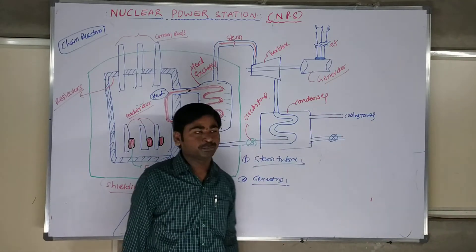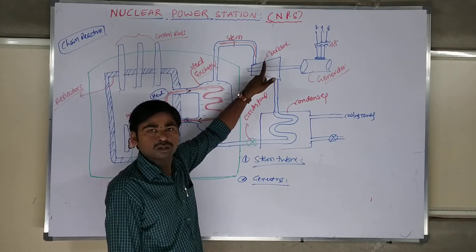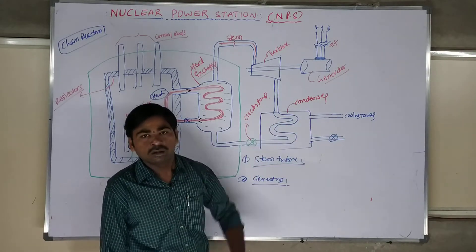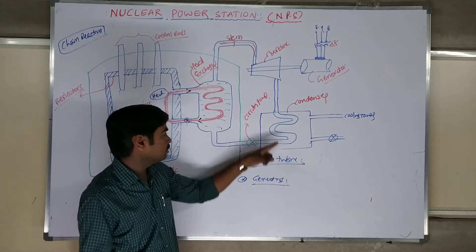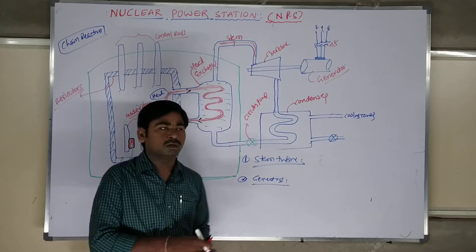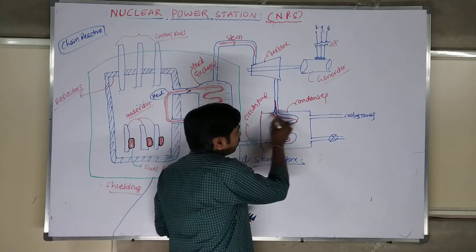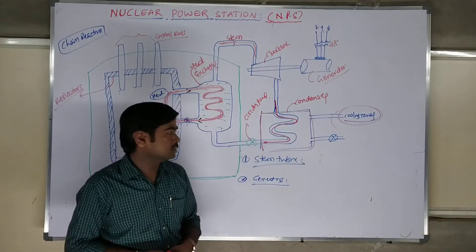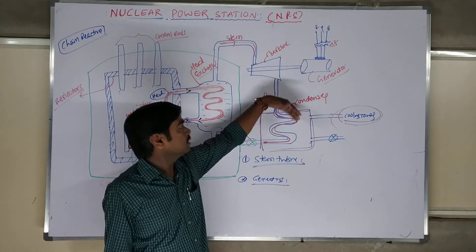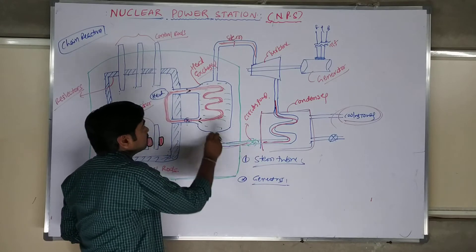We are generating electrical energy to give back for further use. The generator converts mechanical energy into electrical energy and sends it to the transmission lines and transformers. As in a thermal power station, there are low pressure, medium pressure, and high pressure turbines. The high-pressure steam is converted into low-pressure, low-temperature steam and sent back to the condenser. The condenser condensates the low-pressure steam completely into water, by utilizing the help of cooling towers. The condenser converts the low-pressure steam into water, and the same water is sent back via the feed pump into the heat exchanger.